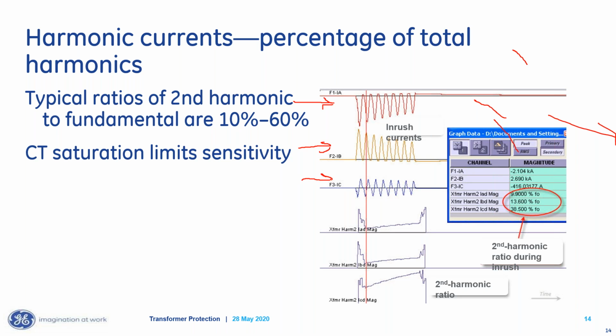If we were looking at the other side of this transformer, the low side breaker is open. This is what we would actually see on the relay. We see these on the relay, but we'd see nothing on the other side of the relay. Because of that, we would misoperate if we don't do something to block this, right? Now, these currents should vectorially sum to zero. We're not breaking Kirchhoff's node rule here or creating a perpetual motion machine. But since we're comparing currents on either side, we would misoperate. So we have to prevent that misoperation in some way.